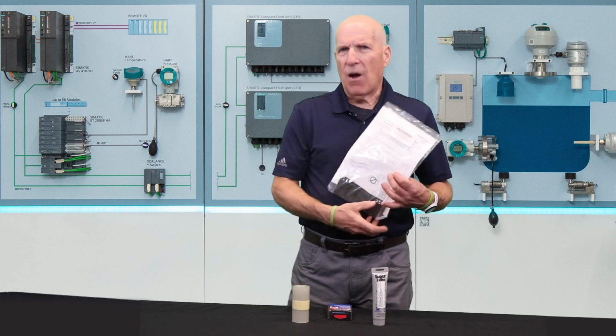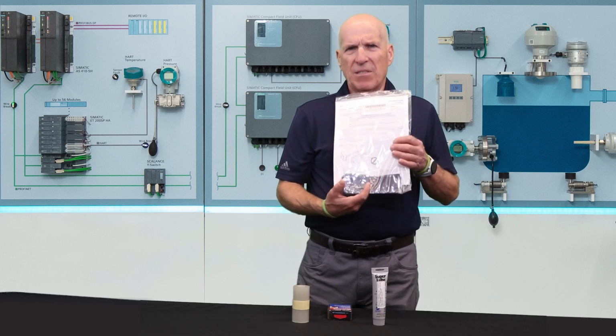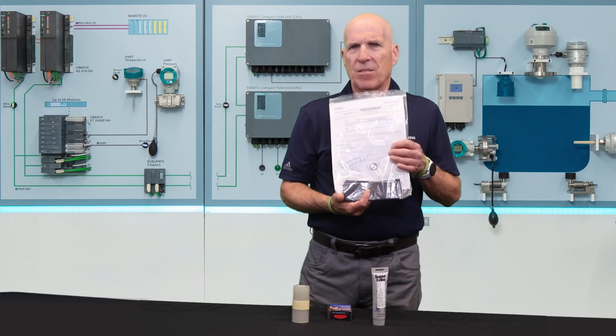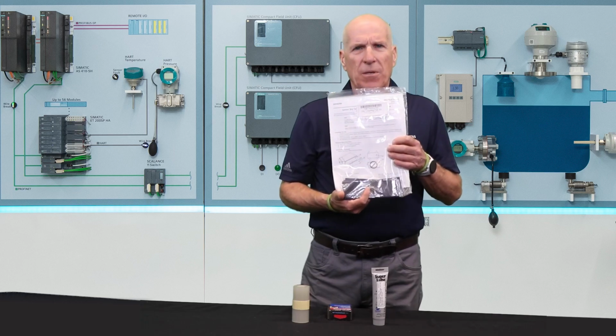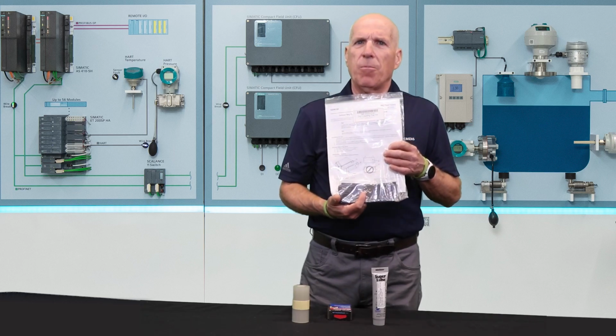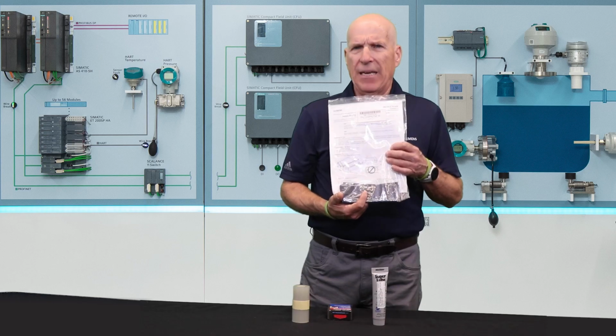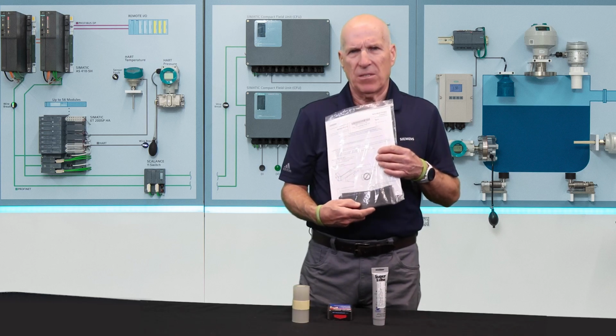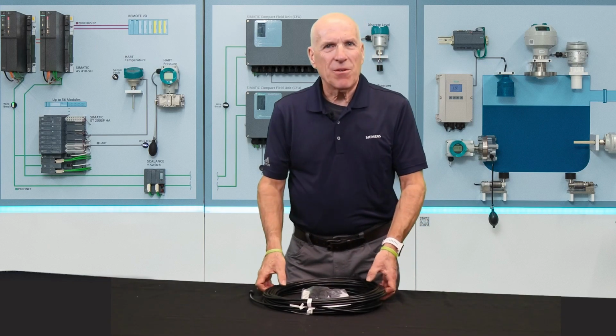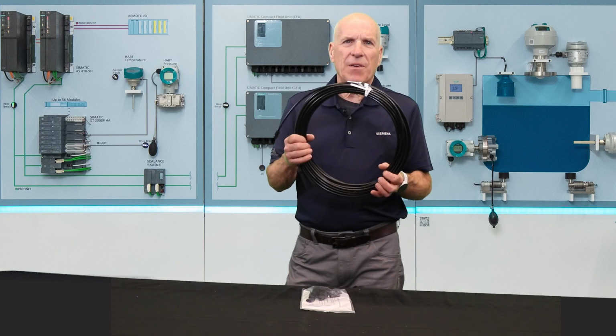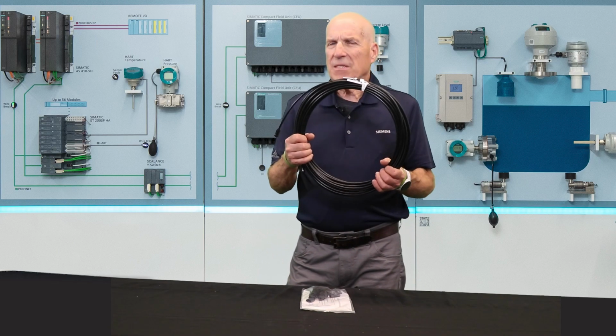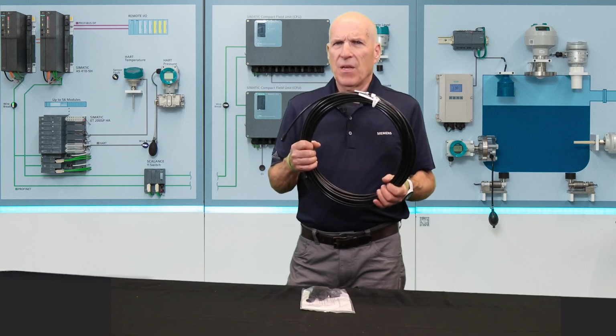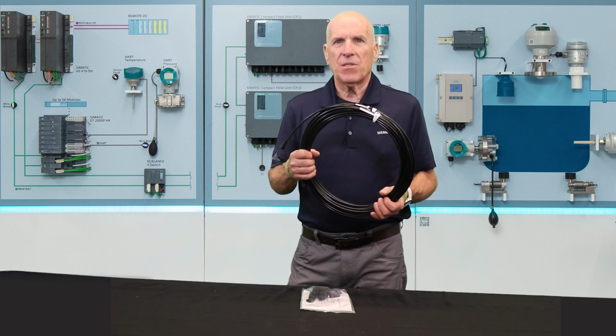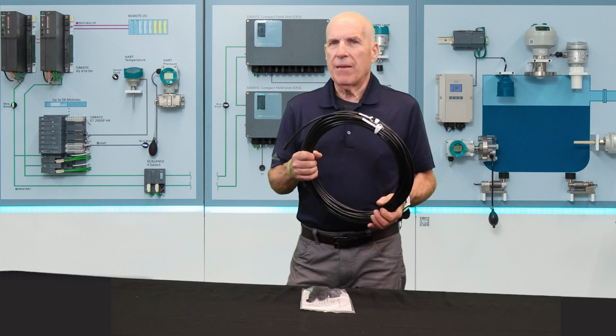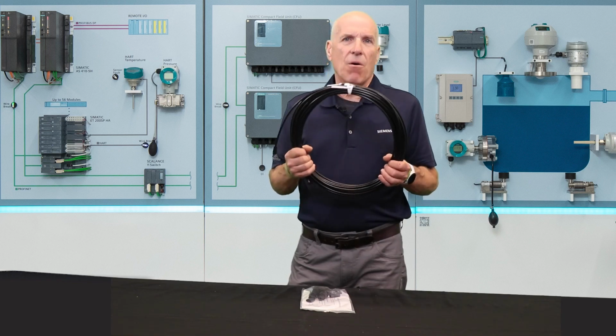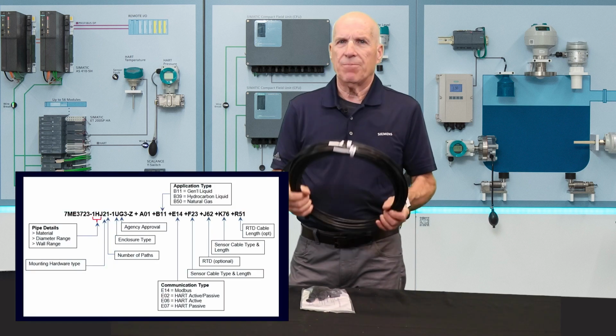Alternatively, if you order dry coupling pads, you'll receive a package of 10 pads. Dry coupling pads offer an alternative method of coupling the sensors to the pipe by taking the place of the standard coupling grease. To connect your transmitter to your flow sensors, you'll receive a set of cables like these. These are standard submersible coax cables. The actual cable type and length you receive will be determined by your order and may be the same, but could be either armored or plenum rated types instead.